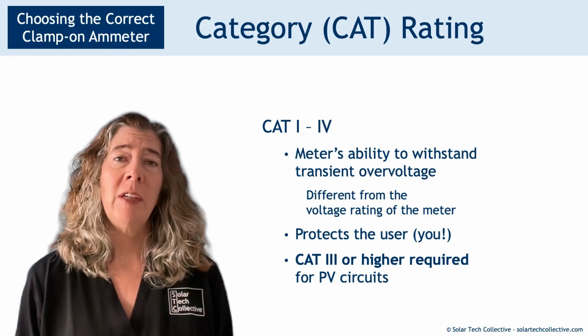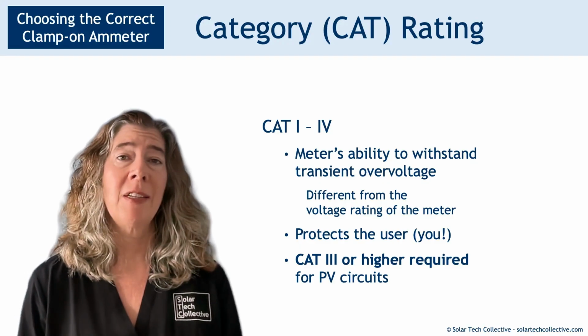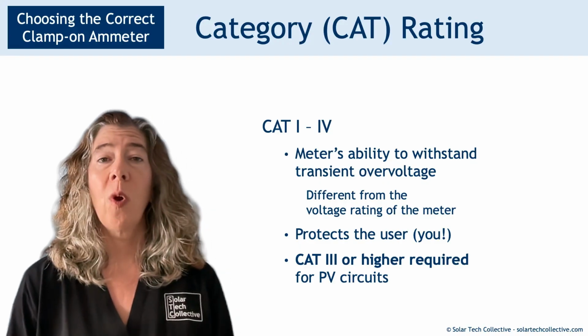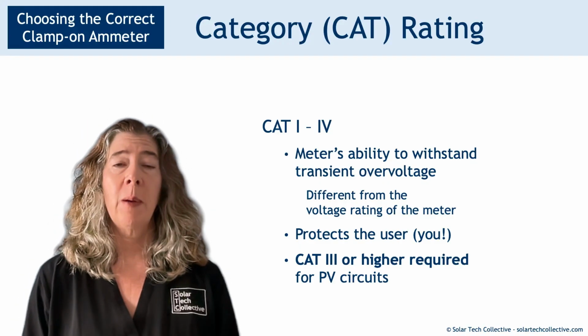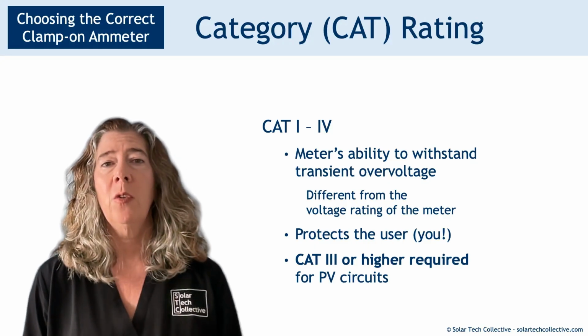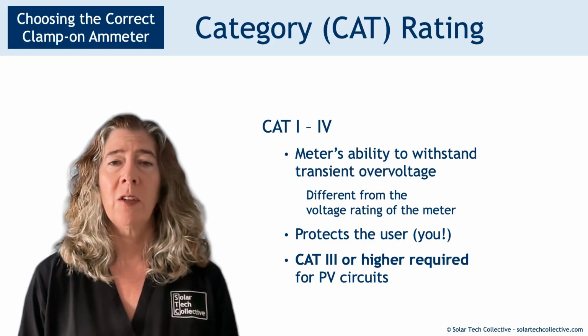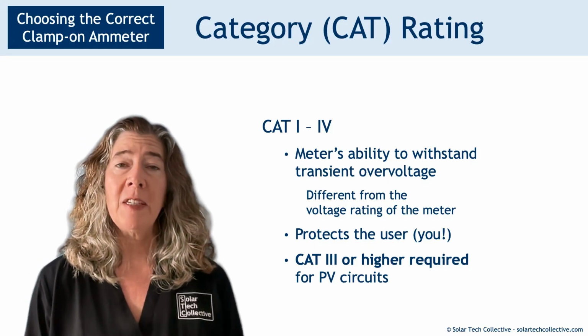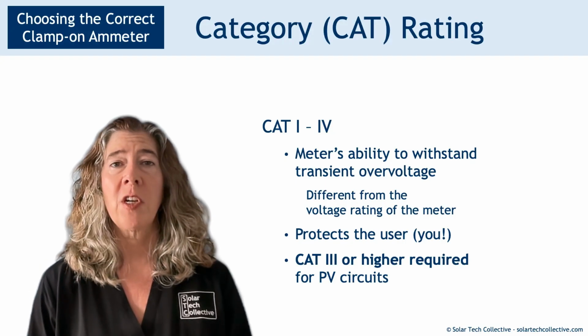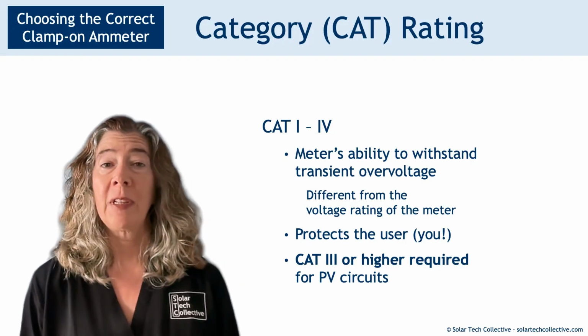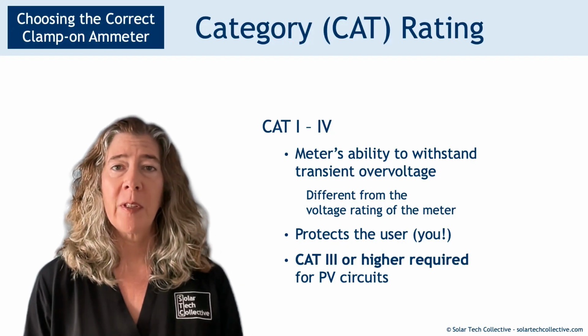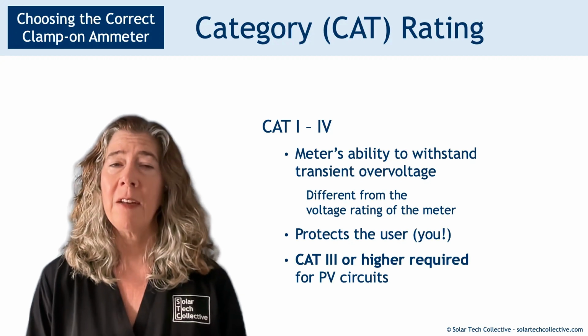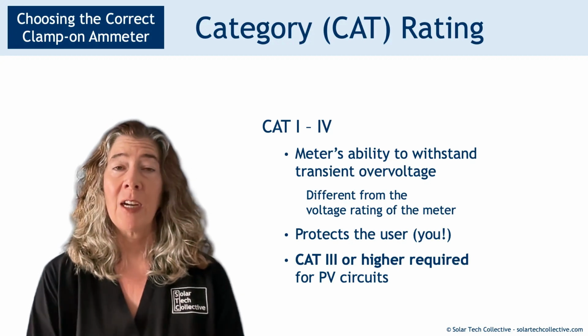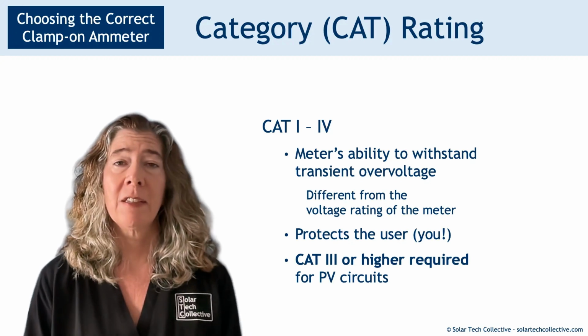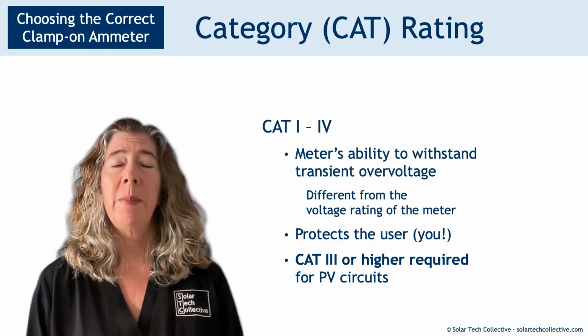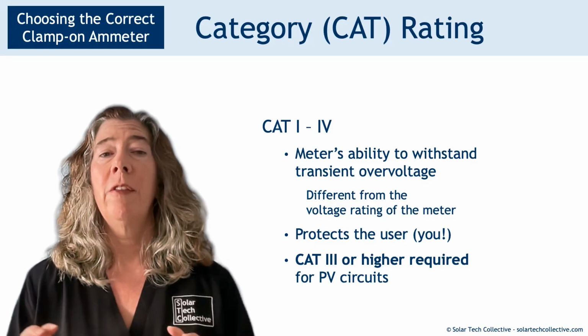There's another rating you need to be aware of for your meter, and that is the category rating, category 1 through 4, which is a measure of the meter's ability to withstand transient overvoltage. What that really means is that if there's an abnormal situation, a voltage surge, maybe from a lightning strike, that is the ability of the meter to withstand that overvoltage, meaning it's not going to explode in your hands. The CAT rating of the meter protects you, the user.